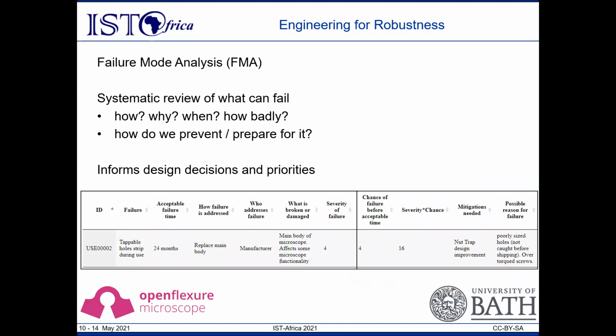A major step we've taken towards this is the beginning of our failure mode analysis, or FMA. An FMA is a systematic review of every stage of the design and manufacturing process, looking at how the microscope can go wrong, why these failures happen, how long is acceptable before the failure is likely to happen, and how severely the failure would impact the user or manufacturer.